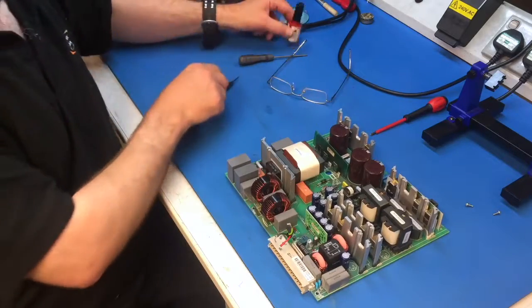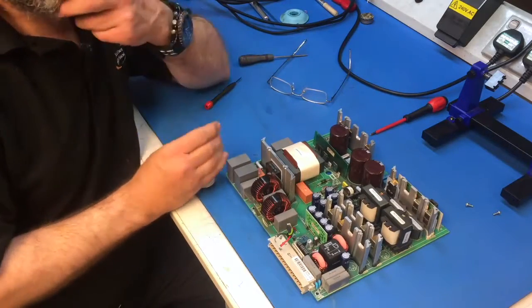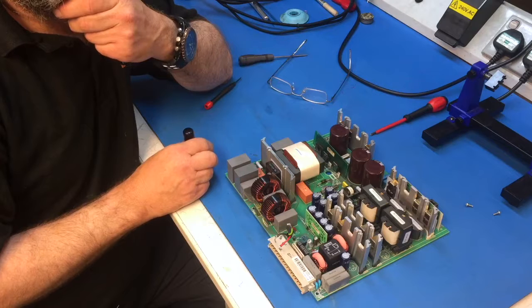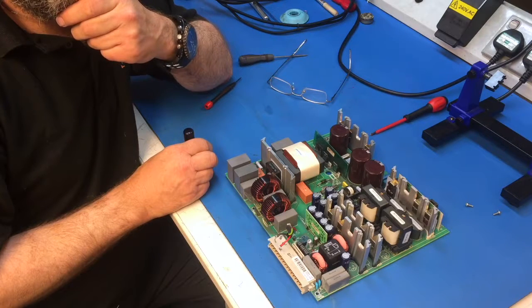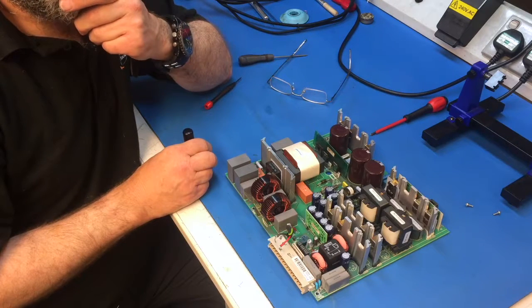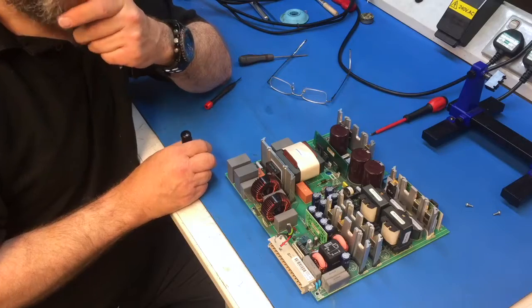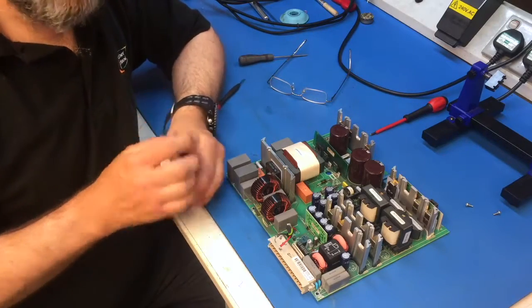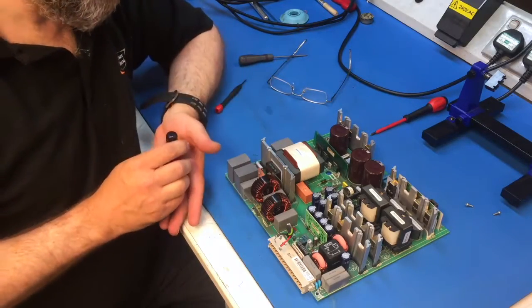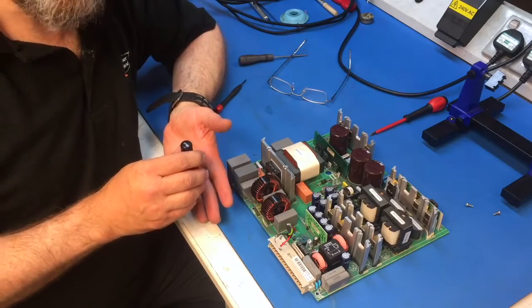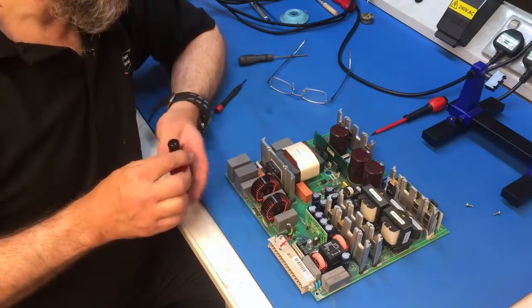So what I get from that is we're not just carrying out a repair of a board, we're fully refurbishing it for any components that will wear, so that we're able to give a guarantee on this board for the customer. Is that correct? Yes, we're trying to make sure that after the repair is done, there's nothing in here that's going to cause a failure within the next few years.